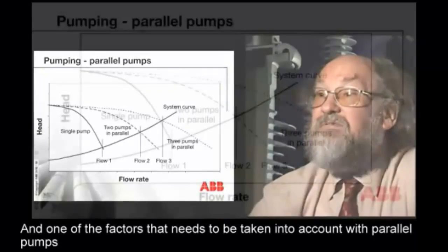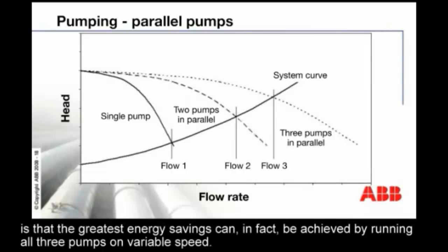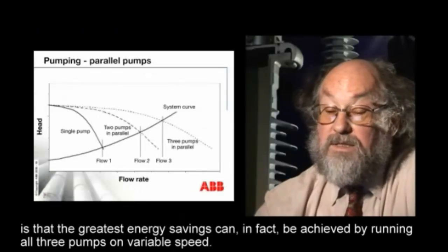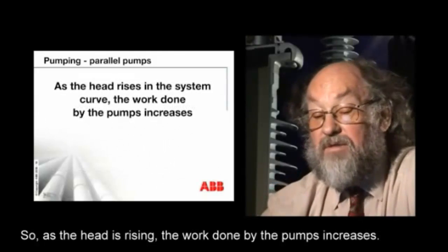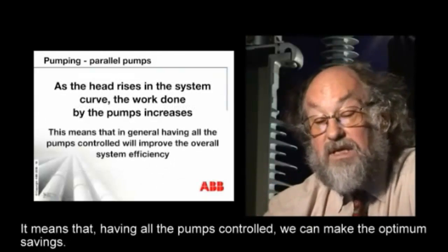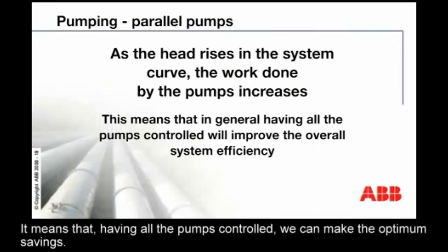One of the factors that needs to be taken into account with parallel pumps is that the greatest energy savings can in fact be achieved by running all three pumps on variable speed. As the head is rising, the work done by the pumps increases, which means that having all the pumps controlled, we can make the optimum savings.